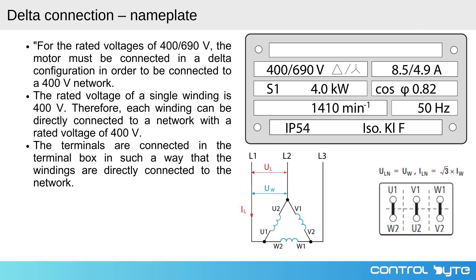This means that each winding experiences the full line voltage, which in this case is 400 volts. In delta, the line voltage UL is equal to the phase voltage Uw. However, unlike in the star connection, the line current IL is higher than the phase current Iw by a factor of the square root of 3.